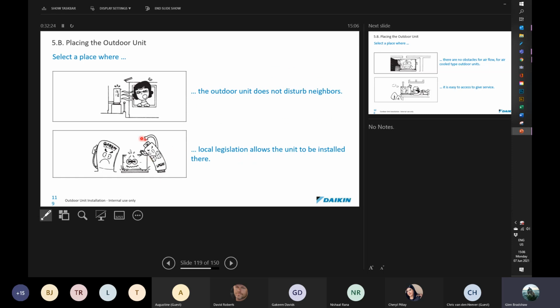All right. So again, I spoke earlier on, but also condensing units, same rules. Check the local legislation. Make sure that the unit can be installed in a position that it's not adjacent to gas installations or gasoline or other products that could be flammable. Okay, we don't want these things mixing. We don't want to start a fire. We're there to air condition and not to destroy property. Okay, so very important that these things are taken note of.